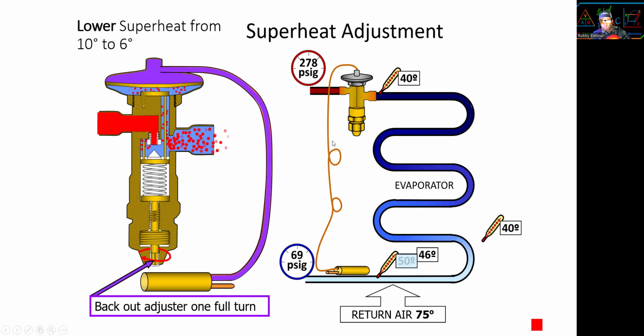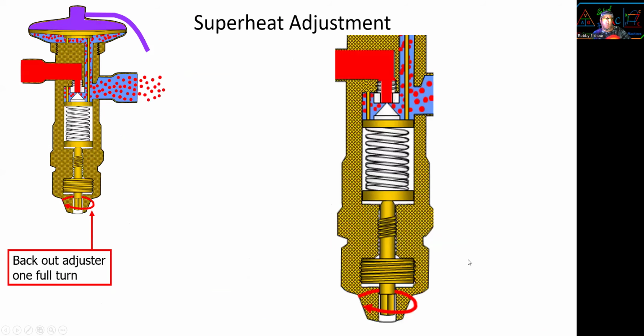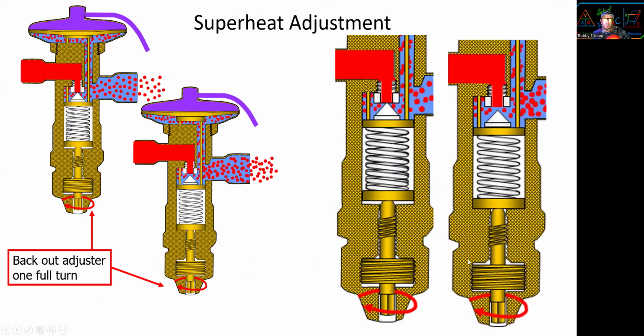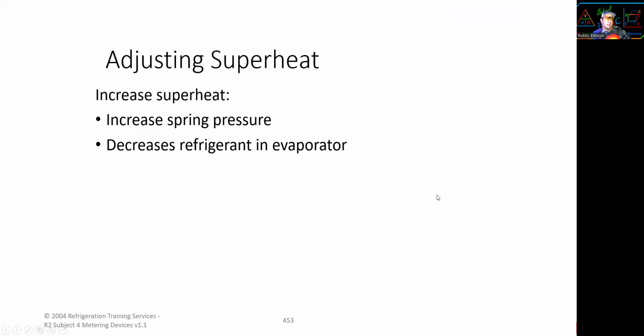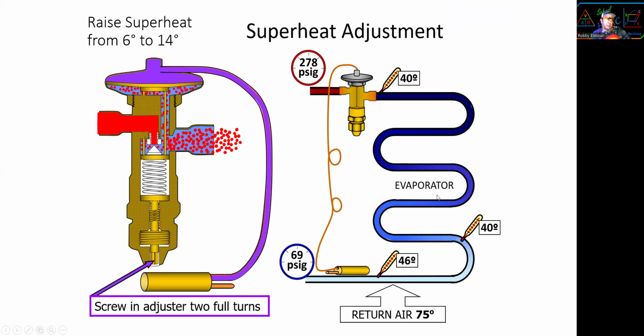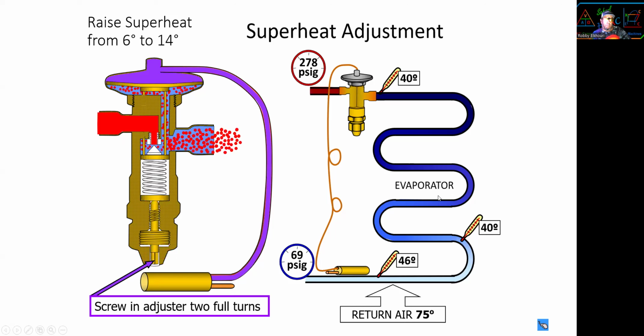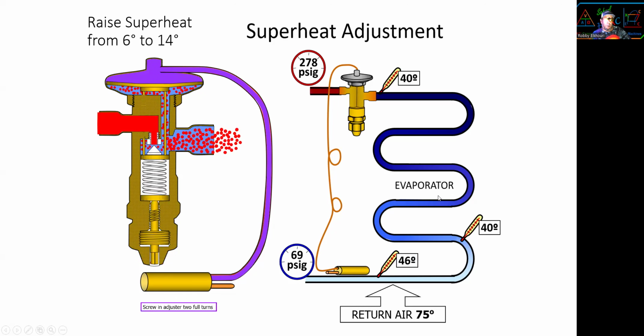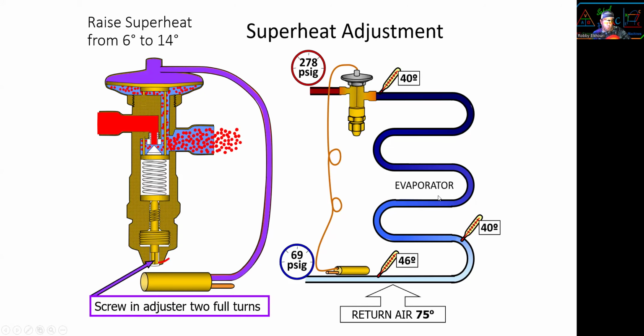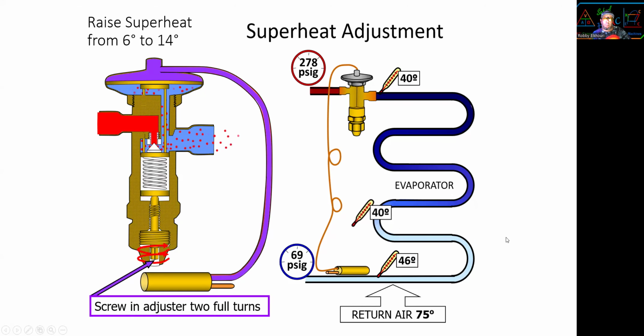When you back out, we'll let more refrigerant in. Look at your liquid level: more liquid. Superheat adjustment. As you can see, you move it, and it will open more. Okay, I screw in. Adjusting 2 full turns will cause it to restrict. The liquid level is going to be less. All right, enough of this.